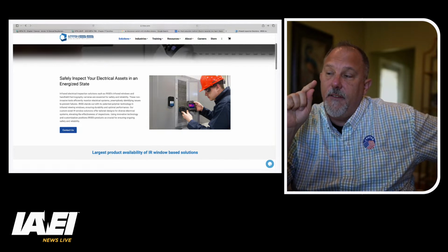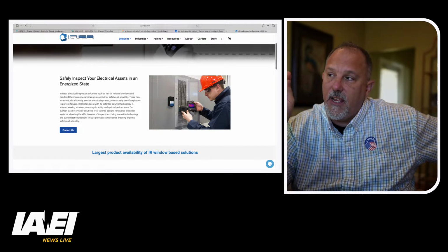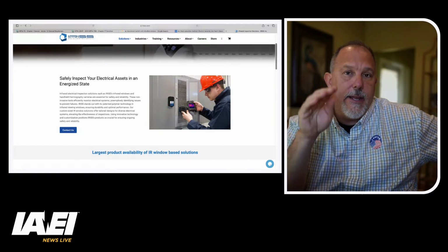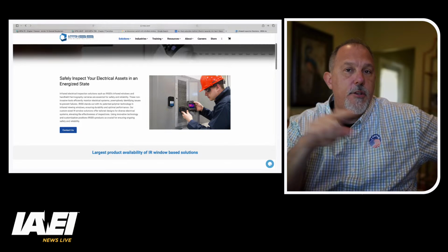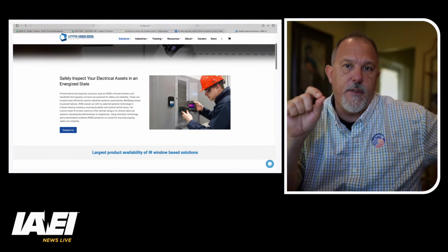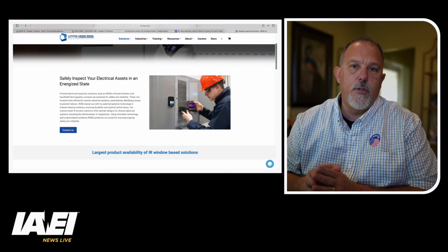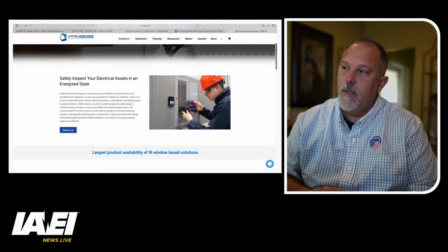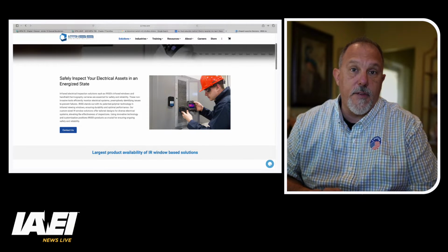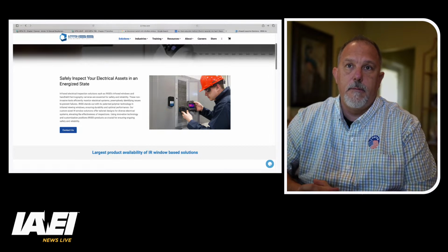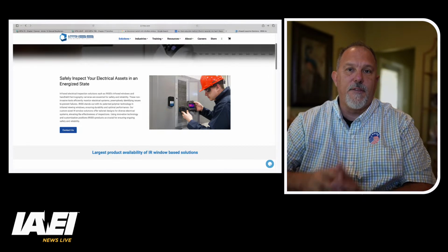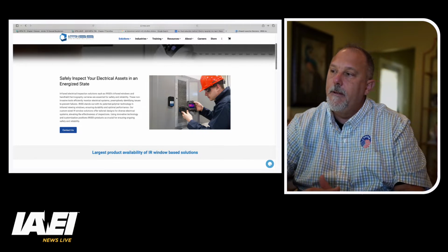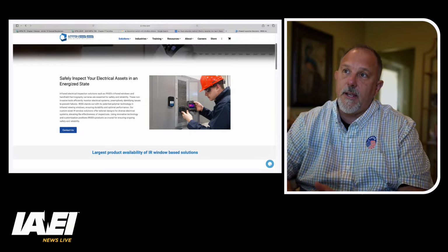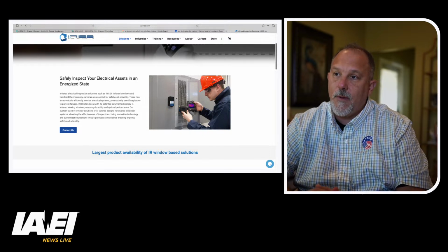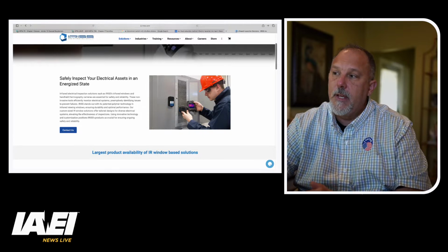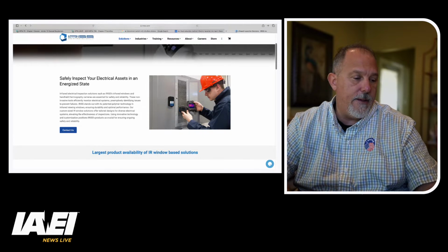So if I employed a technology like this, then I could argue that you would not have to, even in the infrared thermography, I would not have to open the door to perform the thermography. Now, I have to be able to get there in front of the equipment to be able to do the infrared thermography. But again, we're talking about working space. And so I can have a disconnect.